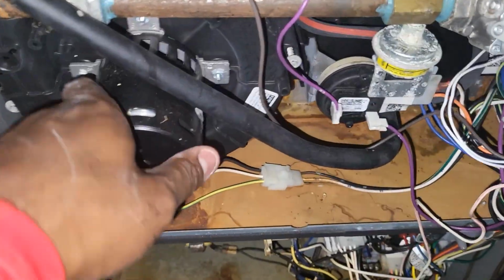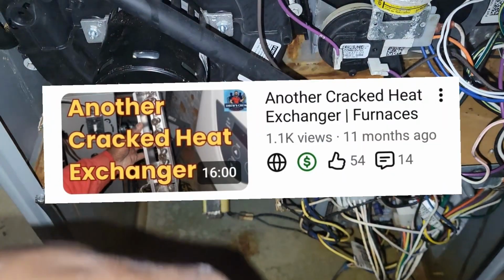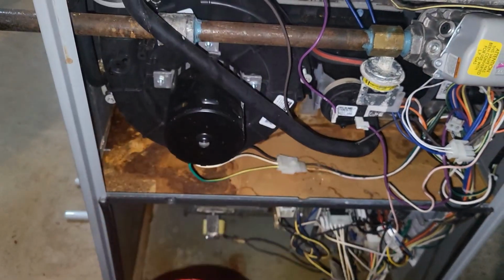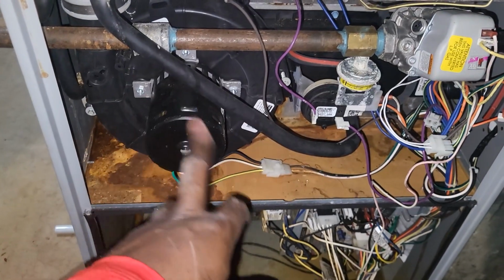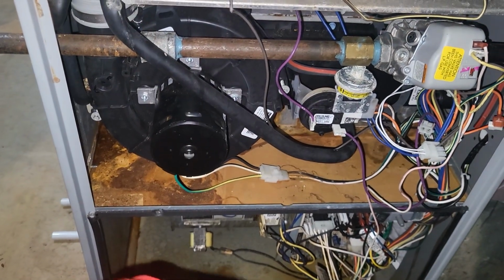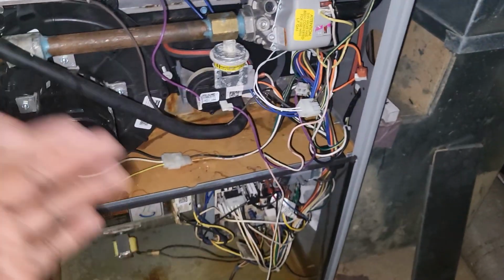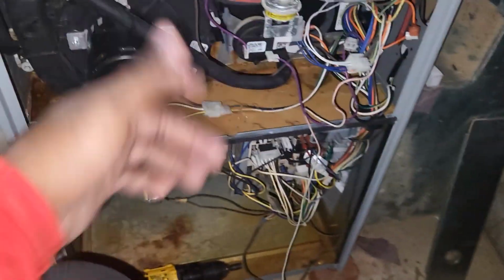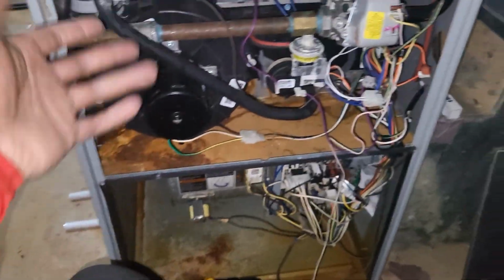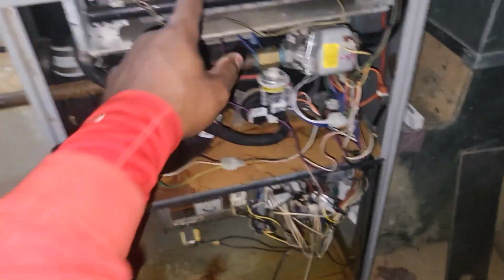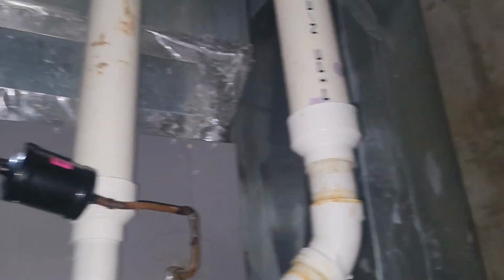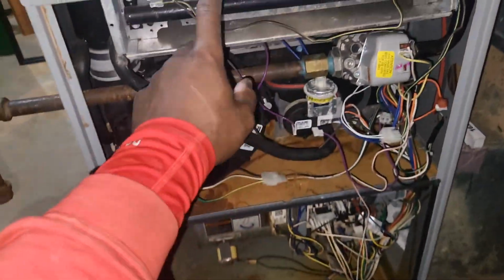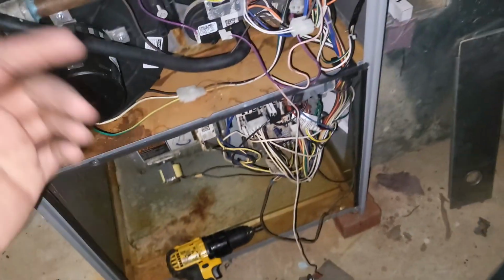But one thing I'm going to bring up, and you guys saw this video from, I believe, last year: when you improperly size a furnace, meaning you didn't know how many BTUs are needed for a residence, and you say, you know what, 120,000 BTUs is nominal. If you grossly oversize a furnace, so instead of this furnace being 90,000 BTU, let's say you put in a 150. For one, it may not work properly because you have to align the ductwork to the airflow of the furnace. I repeat, you have to align and size your ductwork due to the CFM of your furnace or air handler.